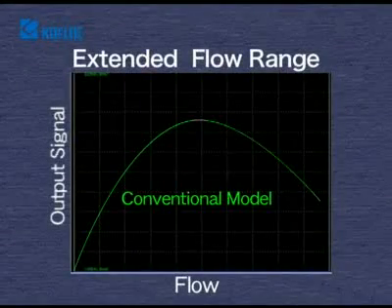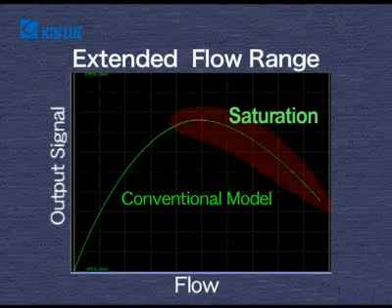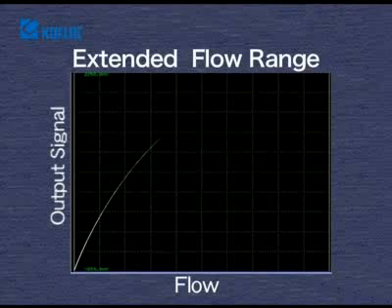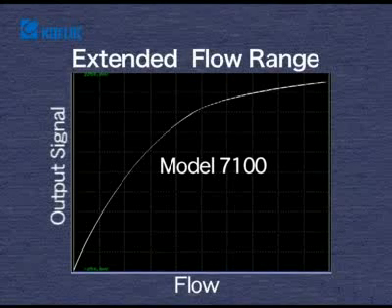In conventional mass flow, the output signal level becomes lower after the flow rate reaches a certain level when gas is allowed to flow beyond the constant flow range. This is the point at which saturation occurs. A new technology has been adopted for the electronic circuits in the model 7,100 series sensor that prevents such saturation.